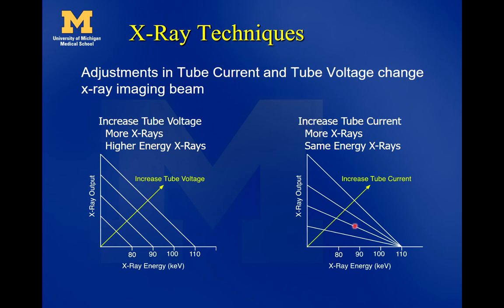In contrast, if we keep voltage fixed at 110 kilovolts and instead turn up the tube current, the maximum x-ray energy stays at 110 keV. The x-ray production stays within the same triangular area, but as we go through different amounts of tube current, we get more or less x-rays out of it.